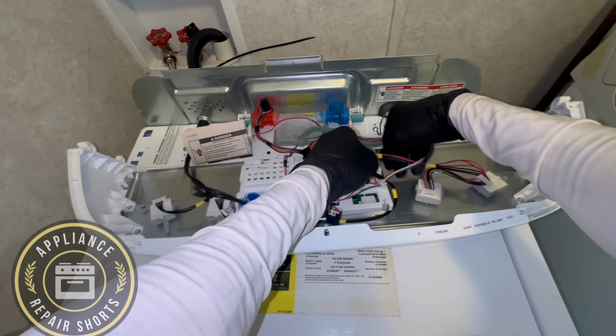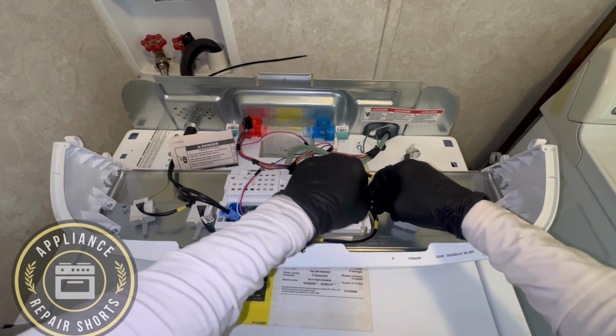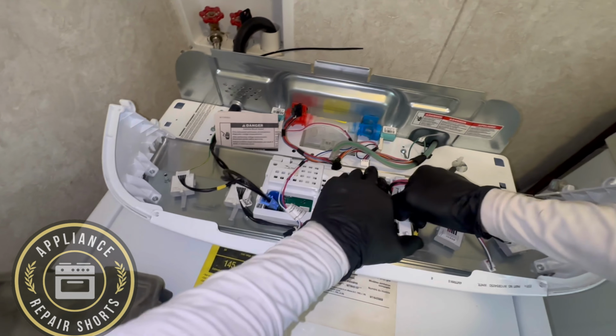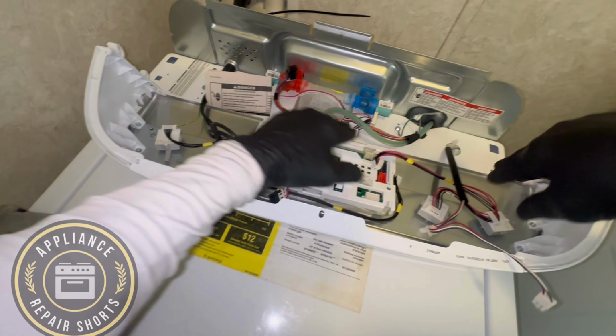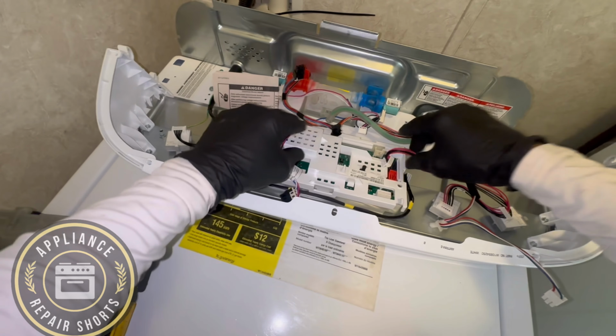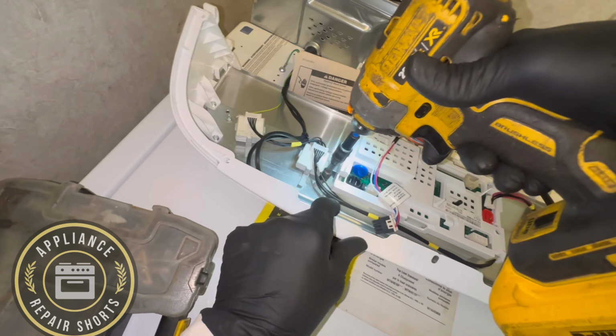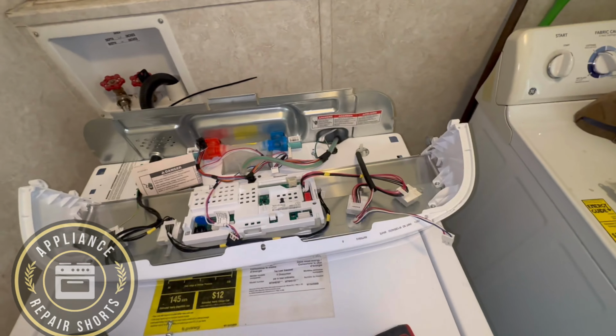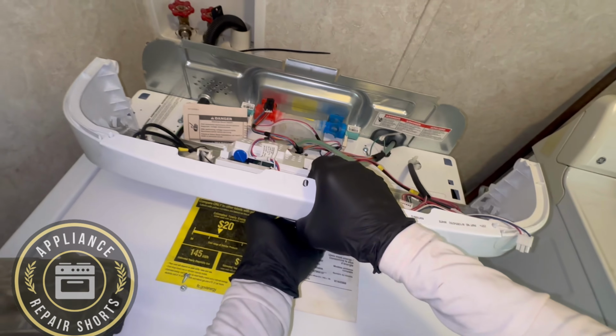So sometimes the transducer is to the point where you cannot get the machine going. If it's damaged, it's damaged, you'll have to replace the board. You can also replace the transducer, that's another option. But for right now, we're going to replace the main board.